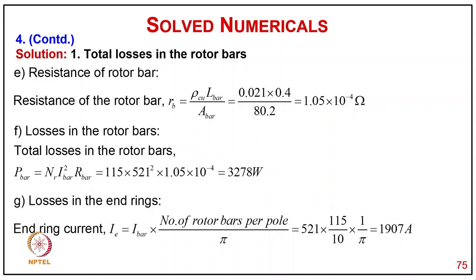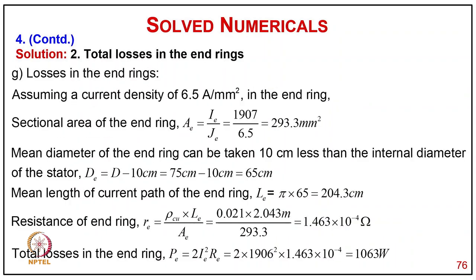Losses in end rings: I bar into number of rotor bars divided by pi, so it comes 1907 ampere. Assuming current density again of 6.5 ampere per millimeter square in the end ring, considering area A equals I upon J E, it comes 293.3 millimeter square.